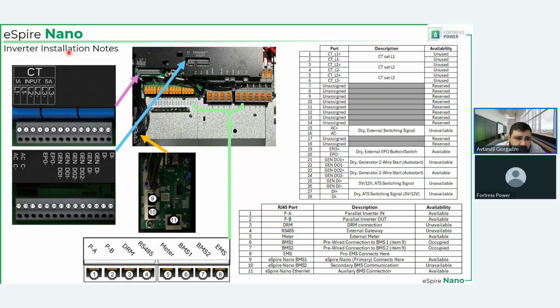Then CT ports, we don't use these at all because remember, we said that we have a meter and that meter communicates here. Where does it communicate? To this port, the meter port right here. How does it accomplish that? We're going to see in the next part. EMS, this is for pro package application only. DRM, unused. RS-485, unused. BMS1 and BMS2 are already connected to this board, to which you are connecting at port number 10 with your primary battery.